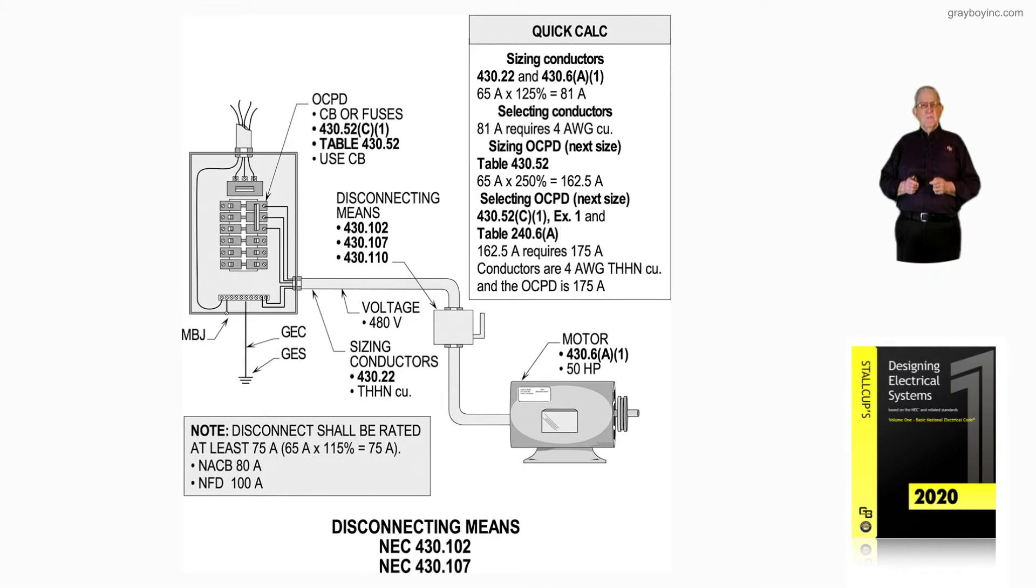This illustration deals with the disconnecting means to a motor in accordance with NEC 430.102, which gives location, 430.107, as well as 430.109A1 and 430.110A. Section 430.107 tells you you've got to disconnect all the ungrounded legs to the motor with the disconnecting means. That's why a controller cannot be used as a combination disconnect and controller.